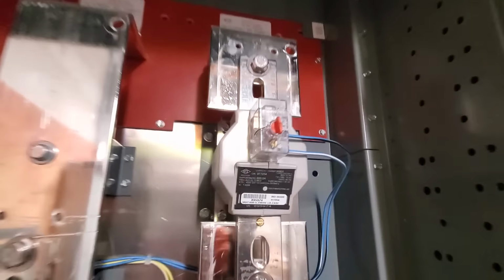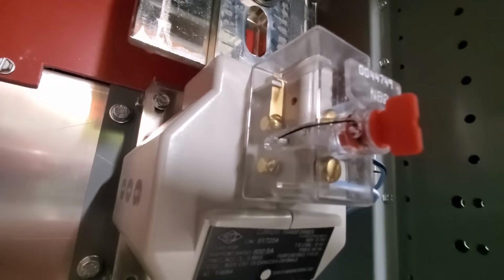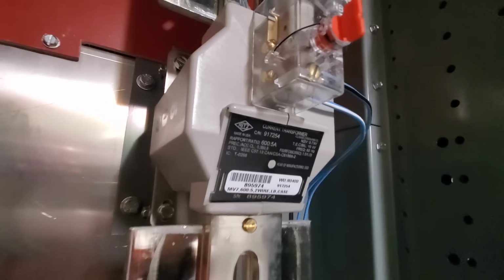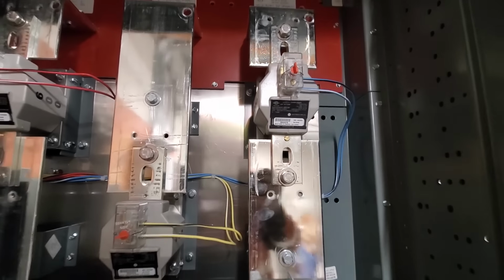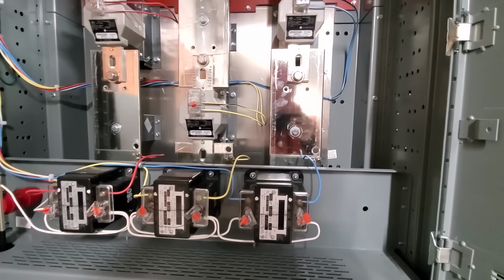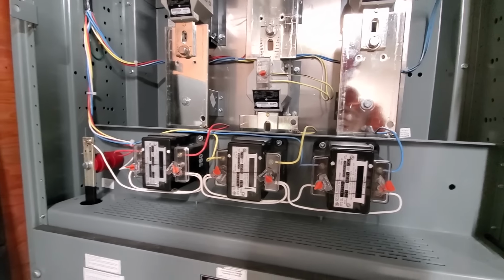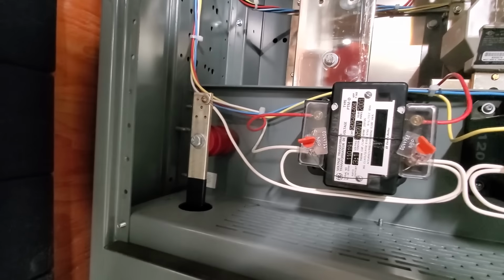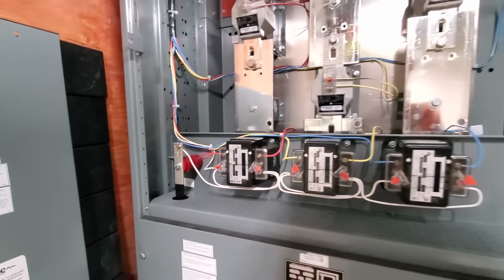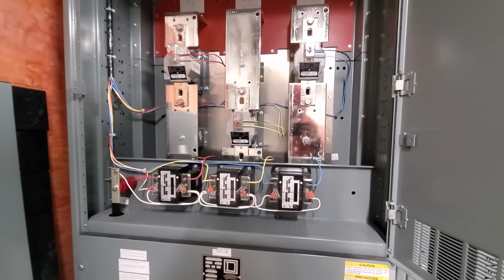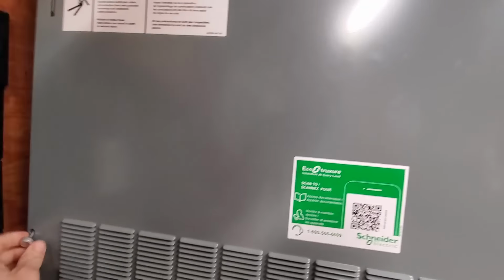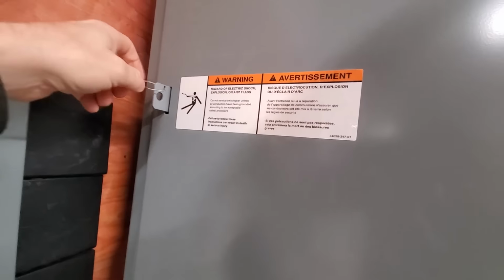Those are 600 amp CTs. I'm just checking to make sure that the jumpers are removed there. So if you've got 600 amps flowing through that, we're going to read it at 5. And these are 3-to-1 ratio transformers that transfer the voltage down from 347-ish to about 120 volts, just so that when that information goes through the meter, it's easily readable through small wiring.